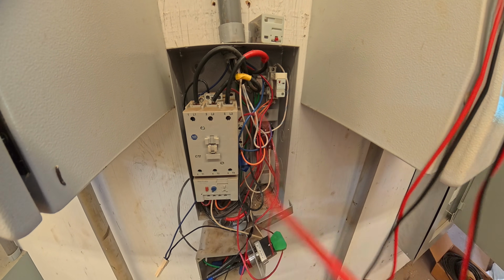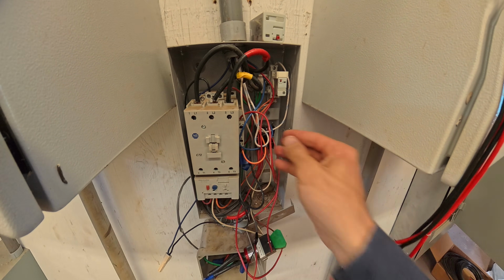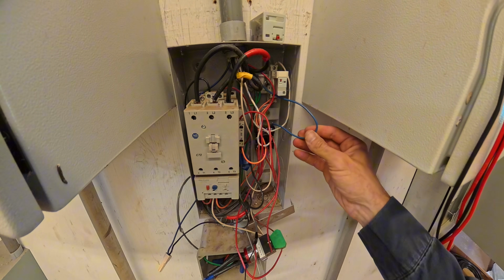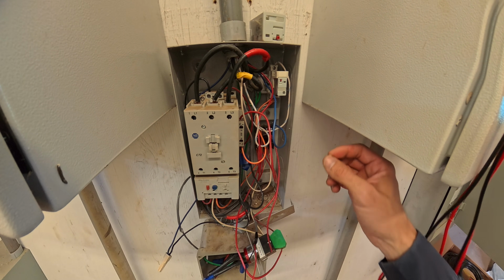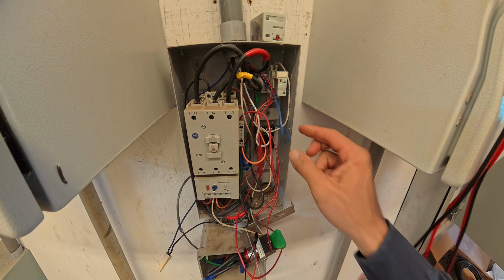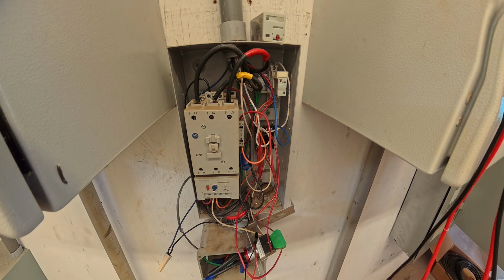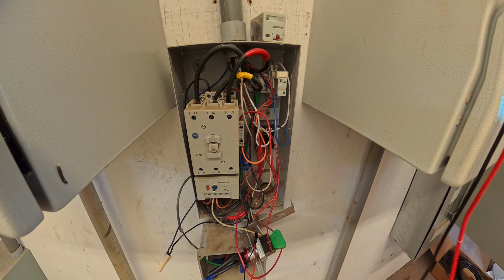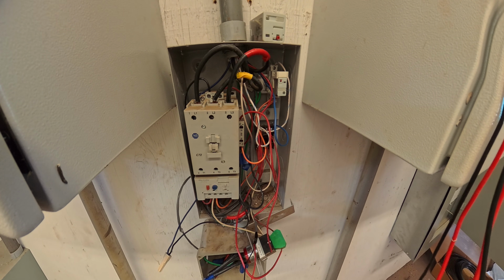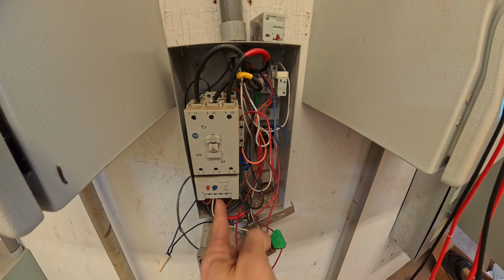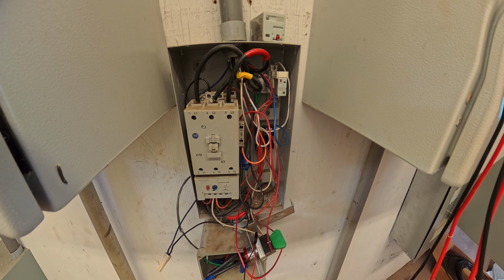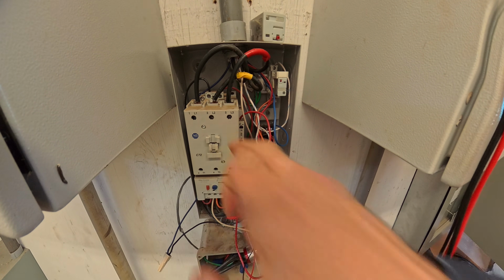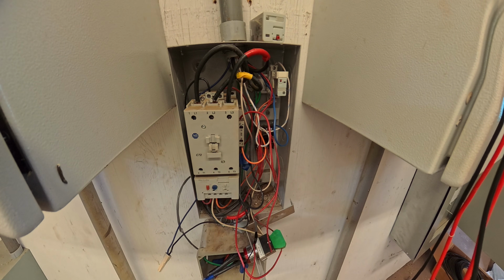That's fine. And then I also want to remove the logic for this relay. The only things I want in series with the coil of this contactor is the discharge temperature switch, the motor overload, and the SCADA system. All those dry contacts I want in series with the 120 coil on this thing.